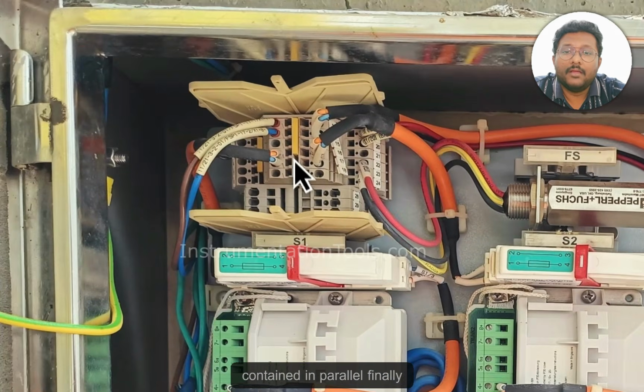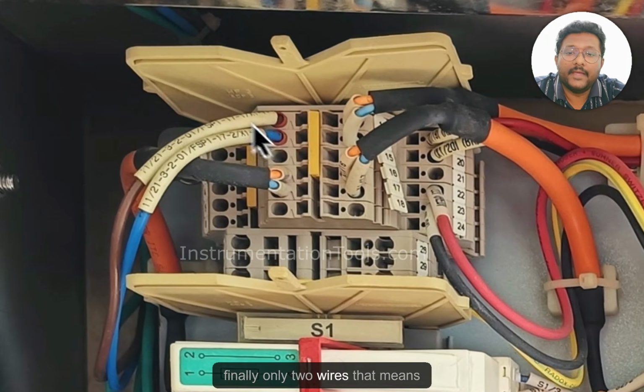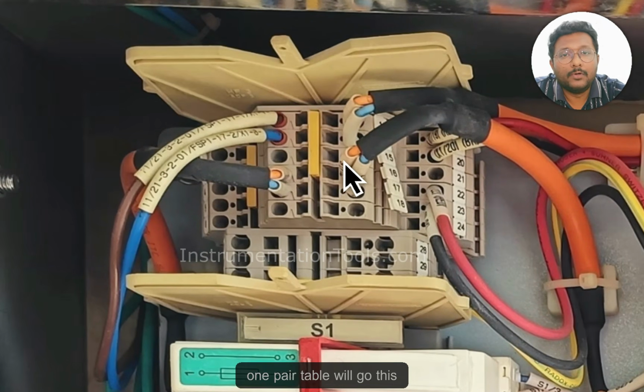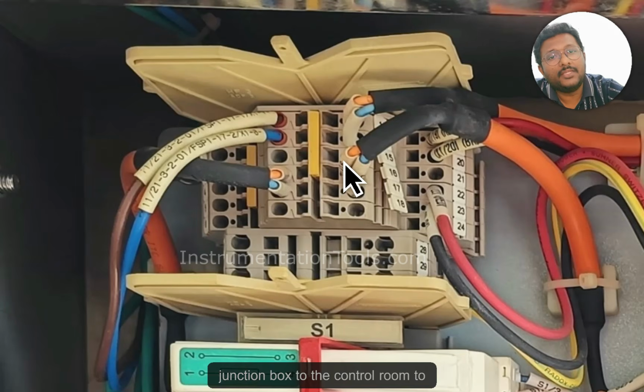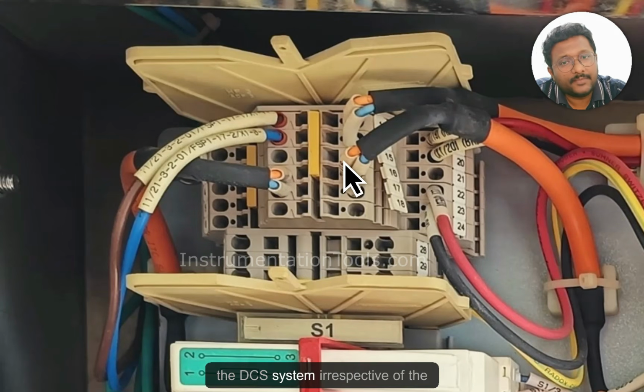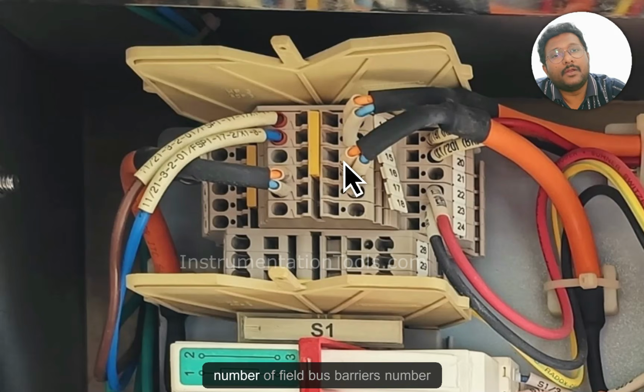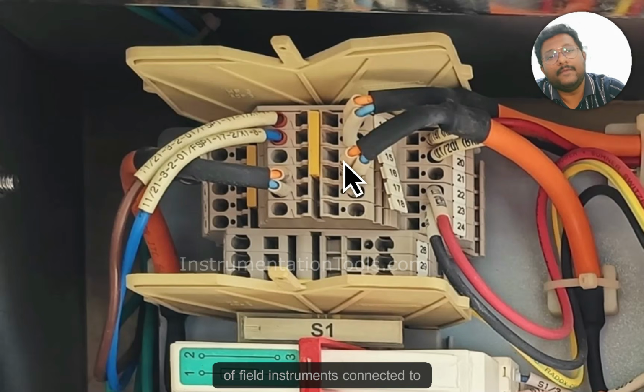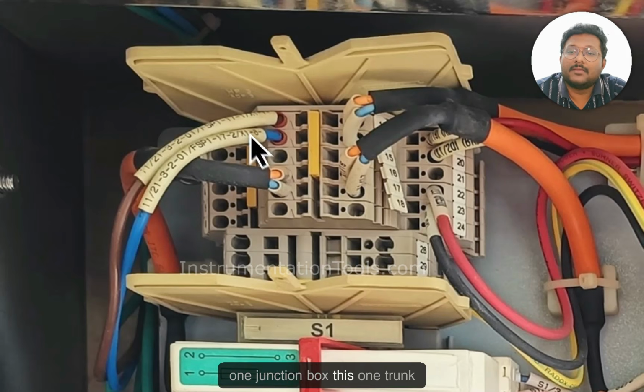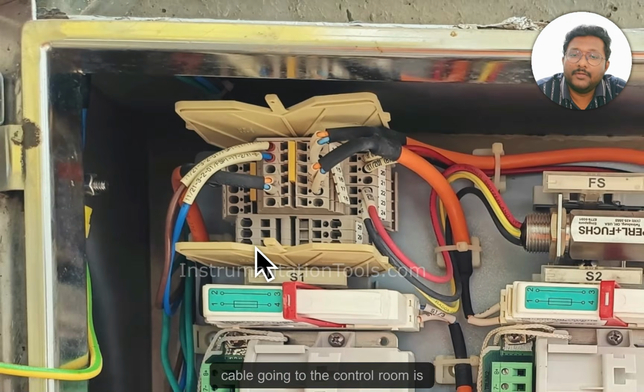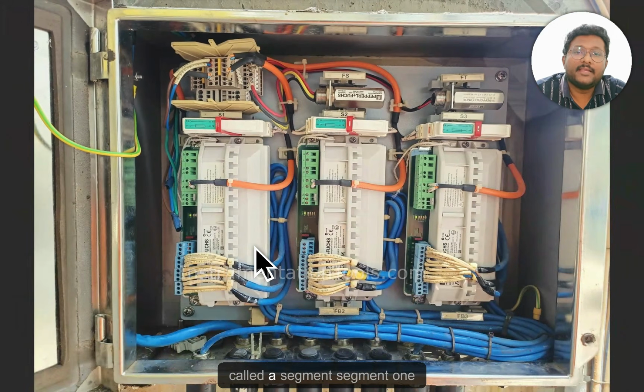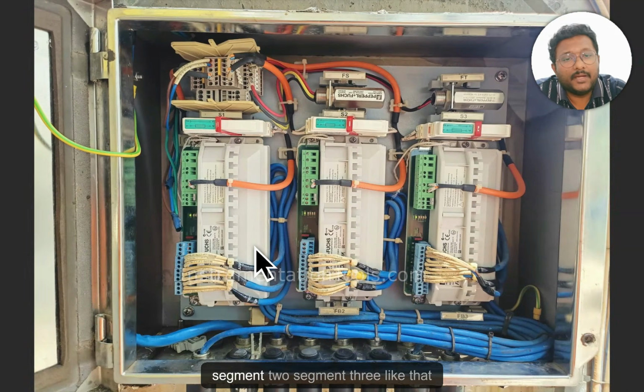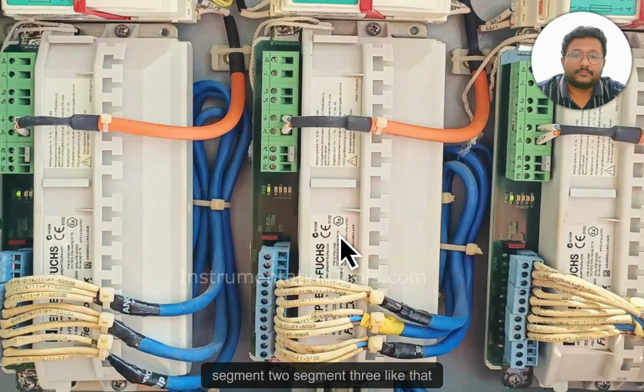Finally, only two wires, that means one pair cable, will go from this junction box to the control room, to the DCS system, irrespective of the number of field bus barriers and the number of field instruments connected to one junction box. This one trunk cable going to the control room is called a segment. Segment 1, segment 2, segment 3, like that.